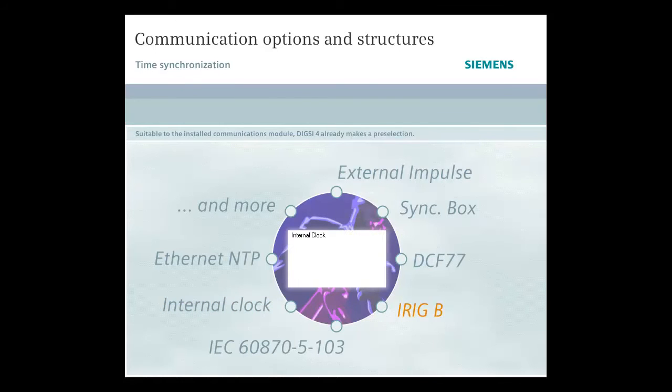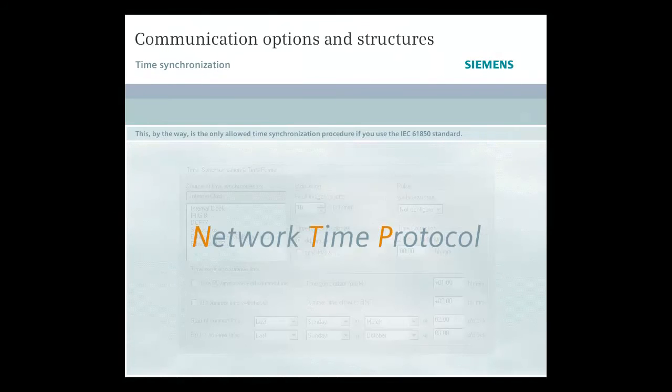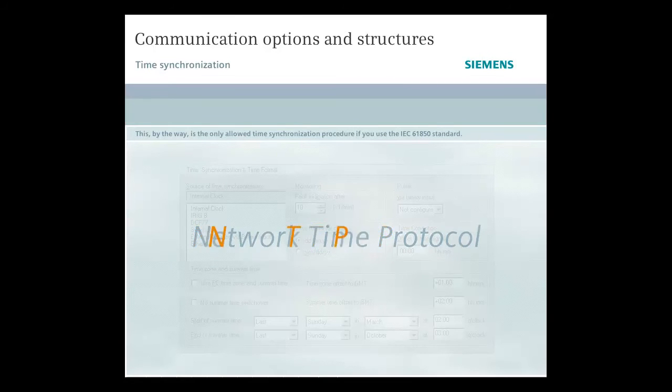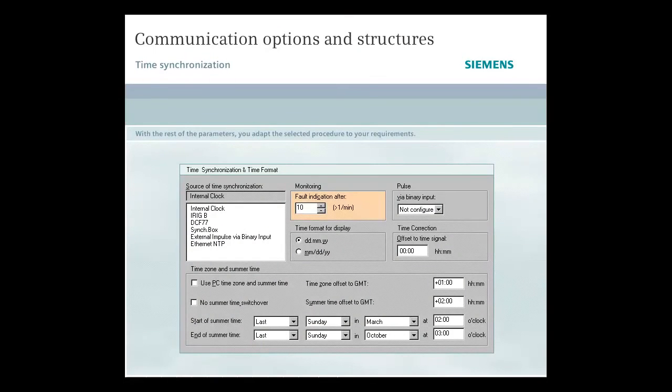Suitable to the installed communications module, DIGSI 4 already makes a pre-selection. For an Ethernet module, for example, you will also find the Network Time Protocol, short NTP, in the selection list. This, by the way, is the only allowed time synchronization procedure if you use the IEC-61850 standard. With the rest of the parameters, you adapt the selected procedure to your requirements. The DIGSI help gives you more information on time synchronization.